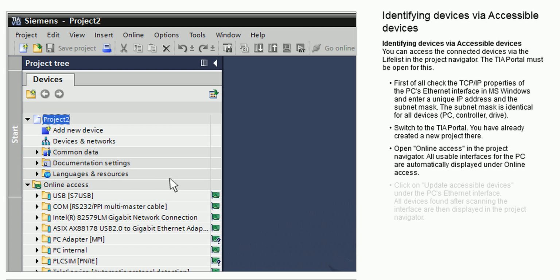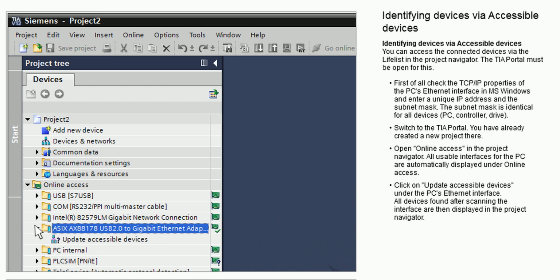Open Online Access in the Project Navigator. All usable interfaces for the PC are automatically displayed under Online Access. Click on Update Accessible Devices under the PC's Ethernet interface. All devices found after scanning the interface are then displayed in the Project Navigator.